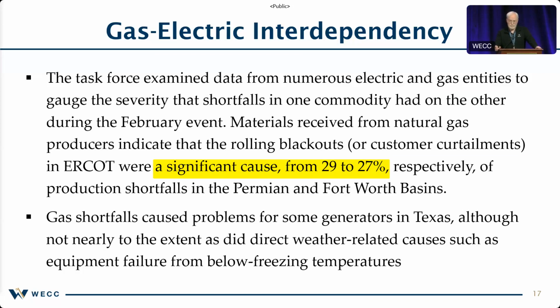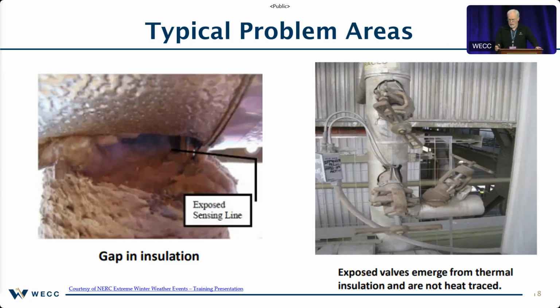In some of the cases, the natural gas company wasn't sure where the electricity came from as far as lines or companies, and the utilities didn't have it on their record that they were serving natural gas supplies. And so the flip side of that, once your natural gas supply starts going down, you start having gas shortfalls to the generation, so you're shedding load because you don't have enough. This is something that we see as we looked at that comparison chart when we went across all five of the events. All five of them had natural gas impact issues, and it was the same type of issue in each one. So the 2011 event also had some training materials and some examples.